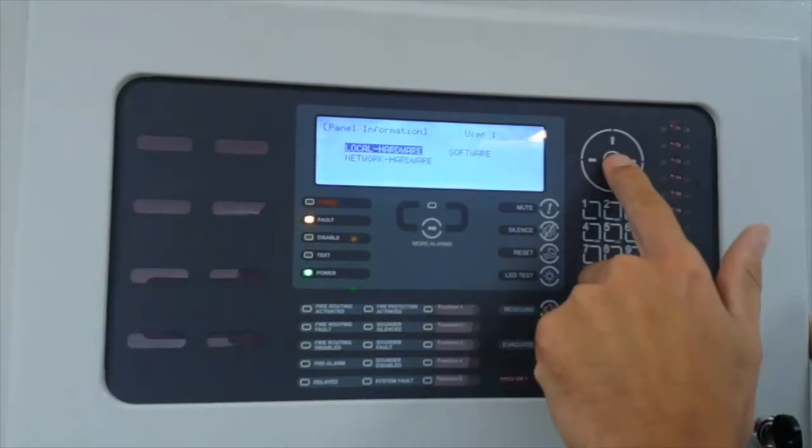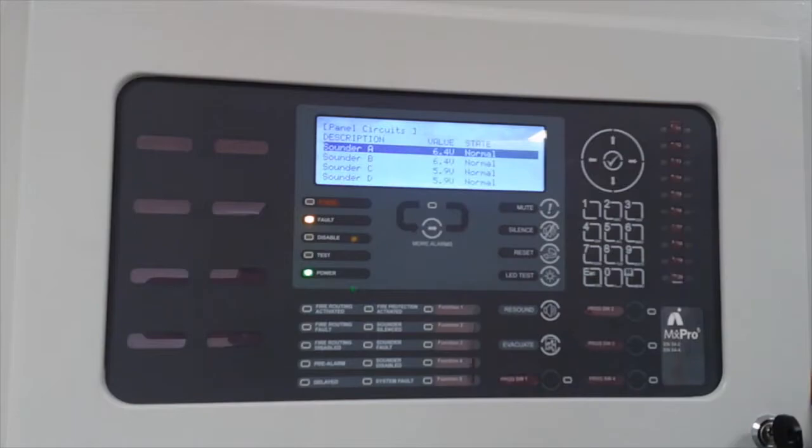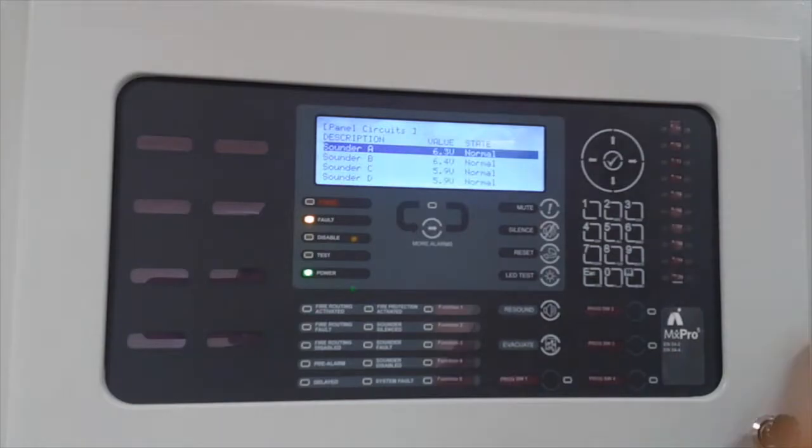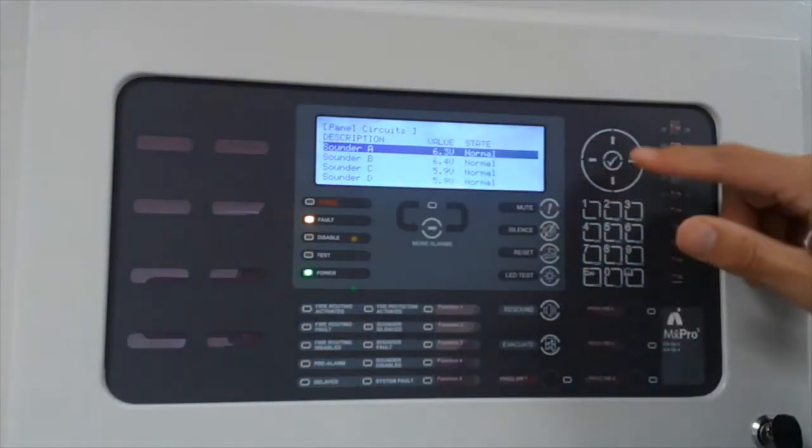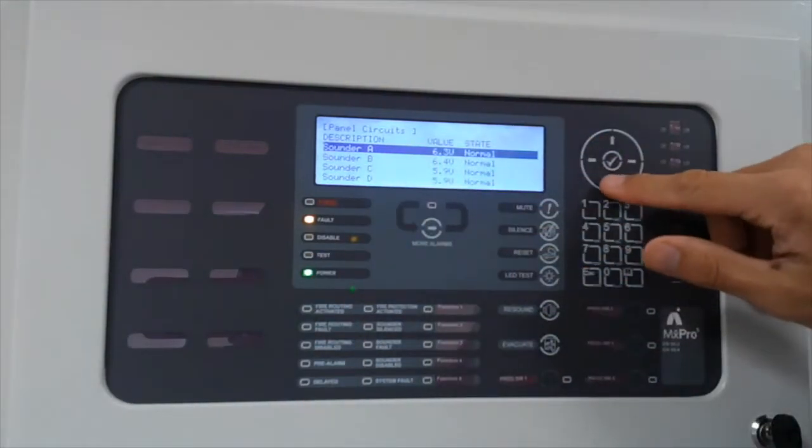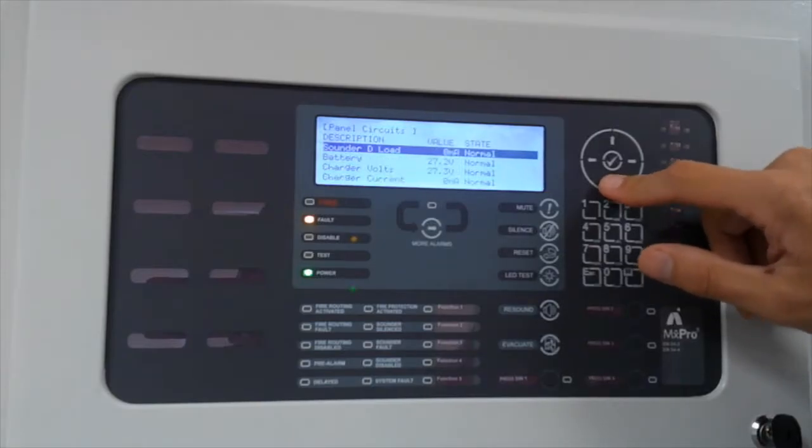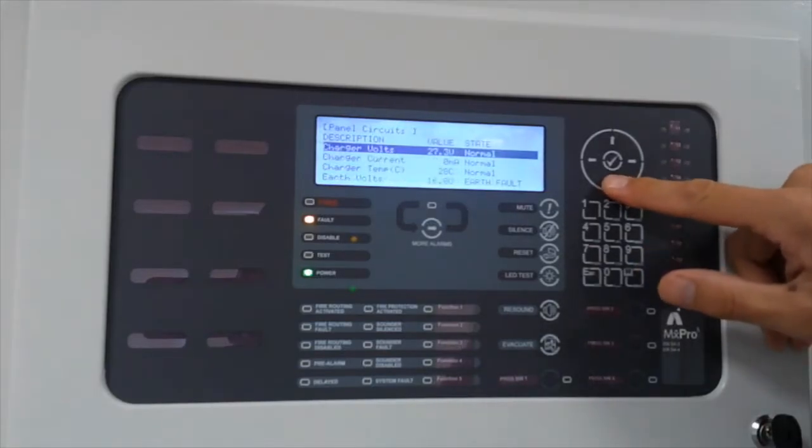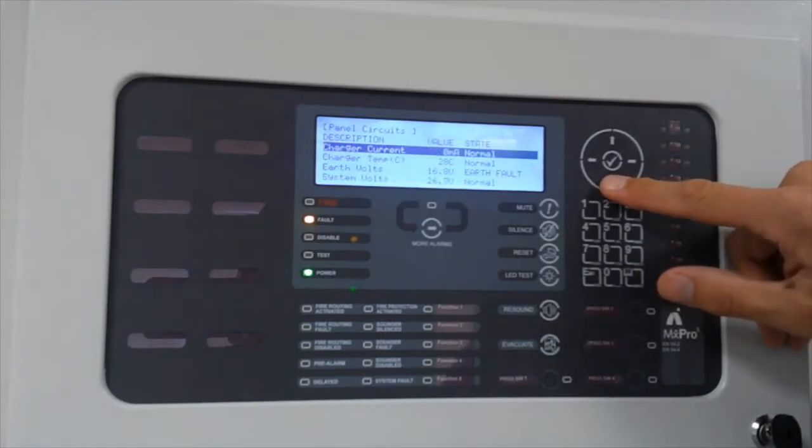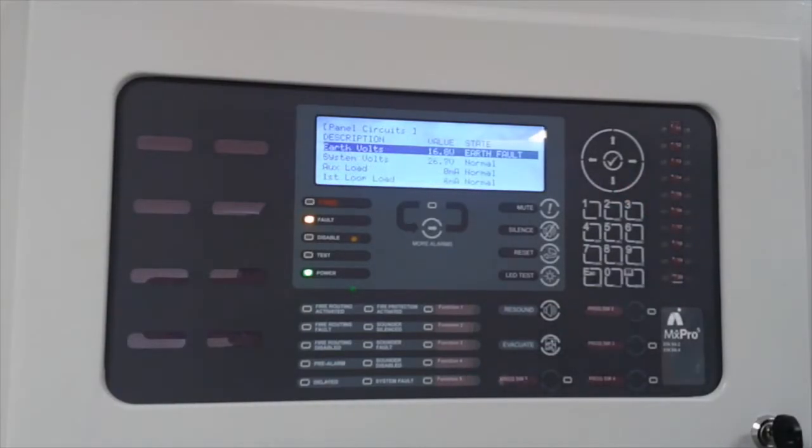If we look at our local hardware, the panel is built with its own multimeter. We can see our sounder circuits, normal operation, scroll down, battery circuit, charging voltage, temperature, and we can see we have an earth fault. Earth volts is 16.8 volts. This is a positive conductor at the ground.